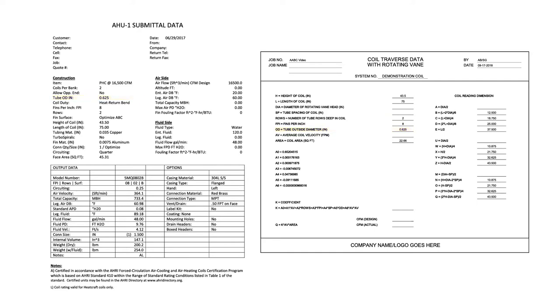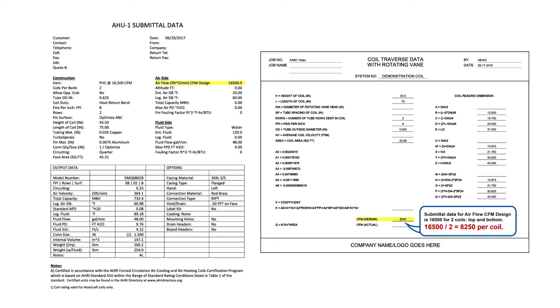On the AHU-1 submittal data sheet, the airflow CFM design is documented as 16,500 for two coils, top and bottom. Therefore, each coil's airflow CFM design is 16,500 divided by two, which is 8,250 CFM for the top coil and 8,250 CFM for the bottom coil.